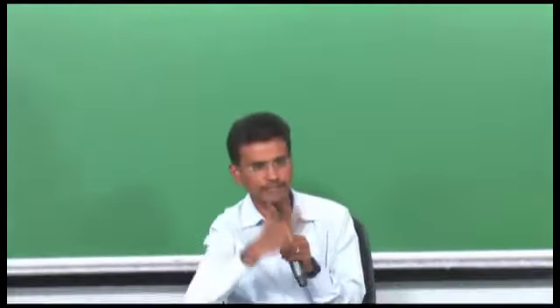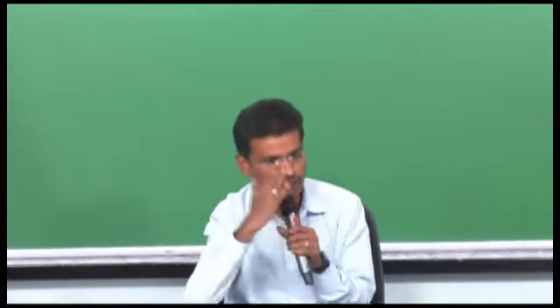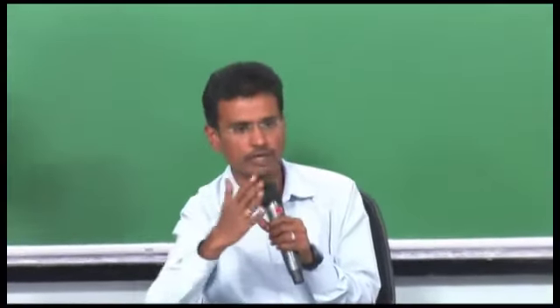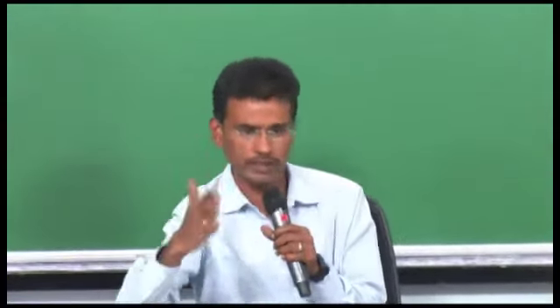In any industry, they will not allow UEL to be formed. That's why they will put detectors, LEL detectors. Normally, gas detectors will be called LEL detectors. For each and every flammable liquid or solvent, there is a value from LEL to UEL level.